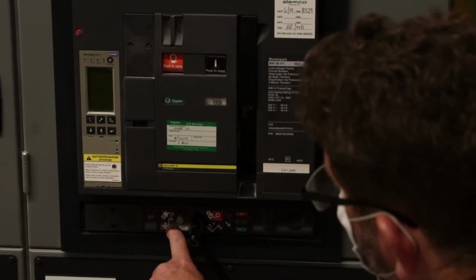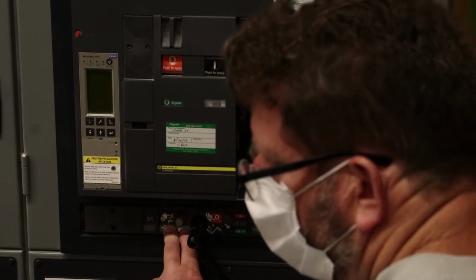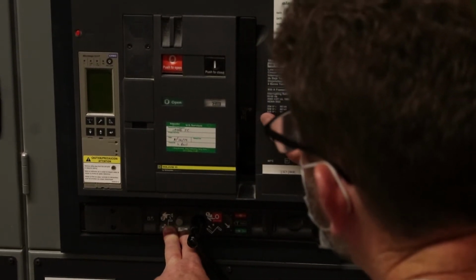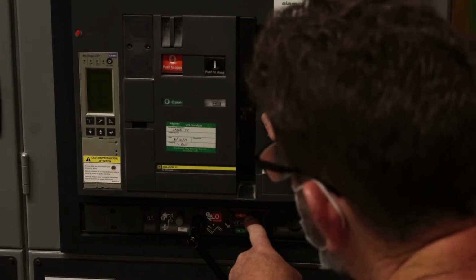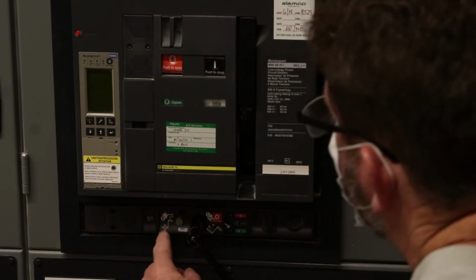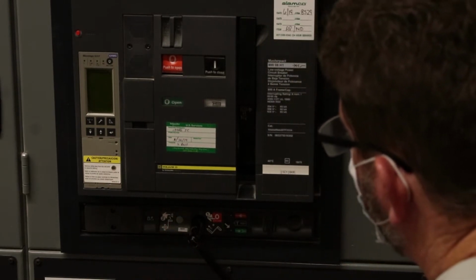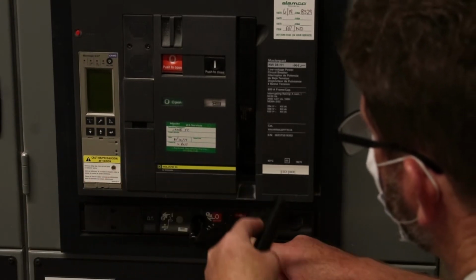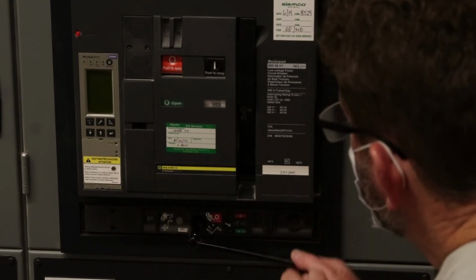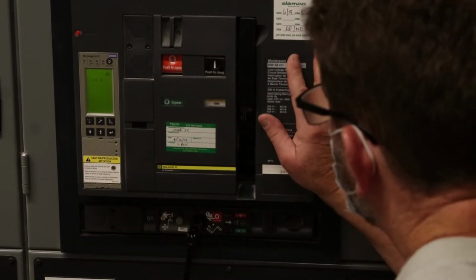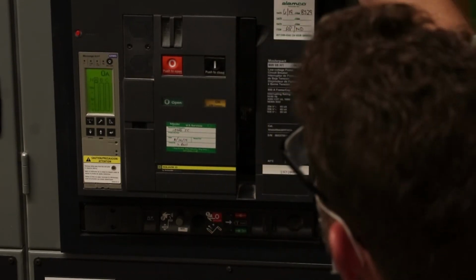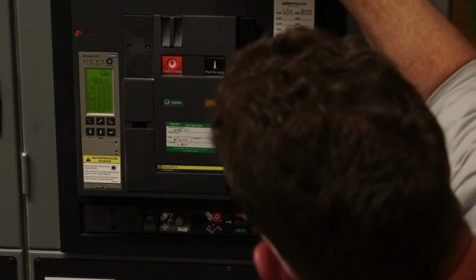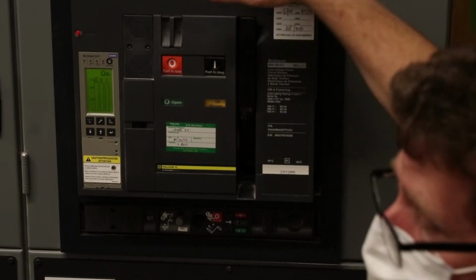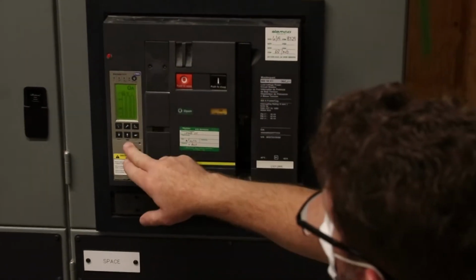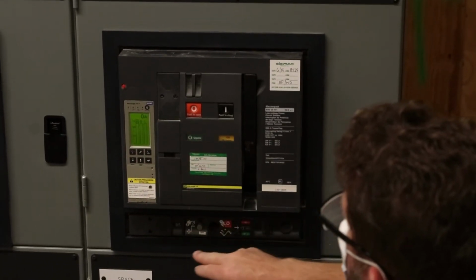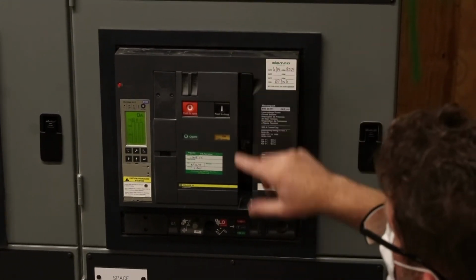Step three is pushing this gray button. This gray button is part of a position lock. It locks it in the disconnect, test, and connected positions. So you want to take it out of the disconnect and bring it into the test position. You push the gray button and start racking the breaker in. As you rack it in, see the arrow come around. What was happening there is its control connections across the top plugged into the top of the breaker. Once they plugged in, you supplied 24 volts DC to this trip unit to light it up, and supplied 120 volts to the spring charging motor. That's why the spring charged.